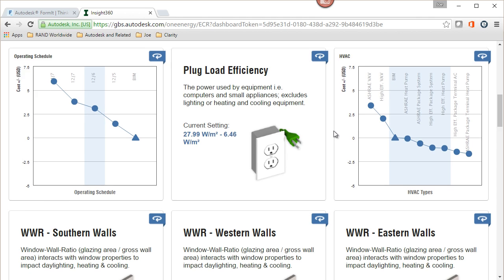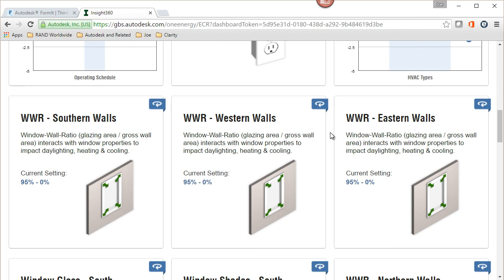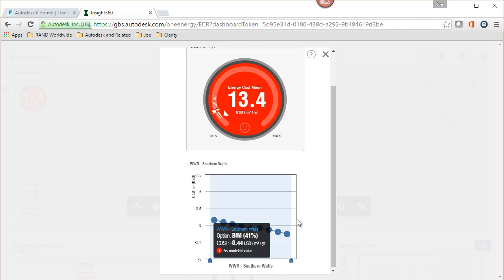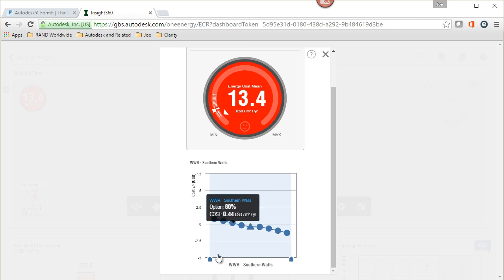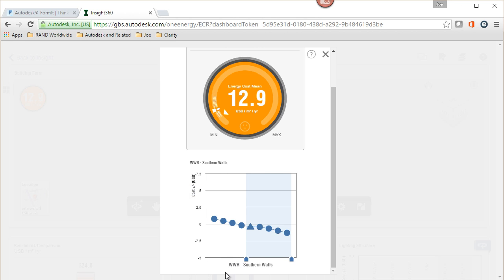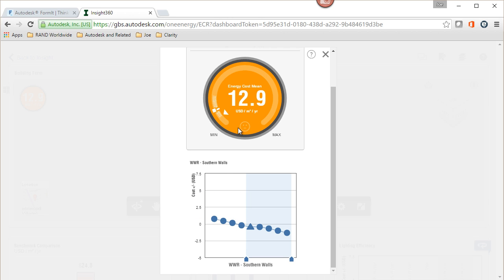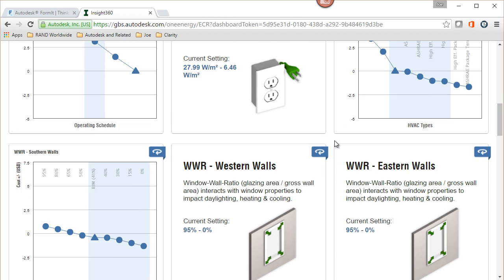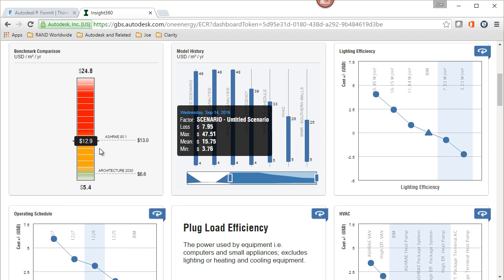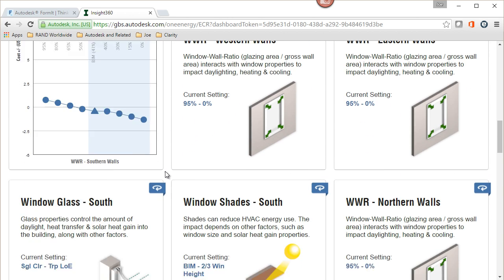What's going to be the window-to-wall ratio for various components of this building? There were defaults that were built into here, but you know, what is it going to be for us? Right now we've got a range where we're saying about 41%. Well, if we know we're not going to be any more than that, we can go ahead and drop that down. All of a sudden our color changed because we're closer to getting to that ASHRAE or 2030 goal. We can see here now we're just below ASHRAE 90.1.